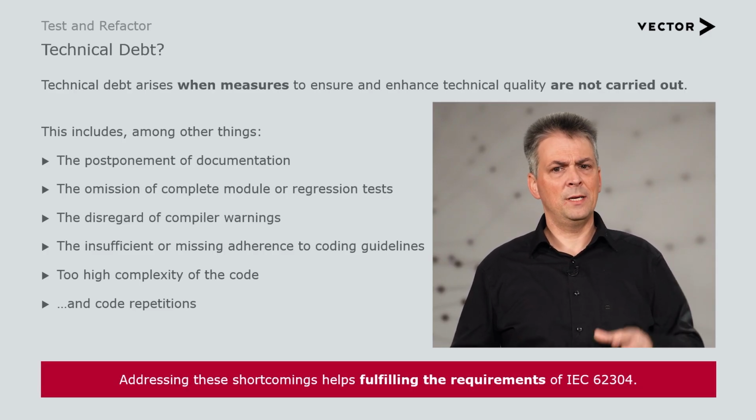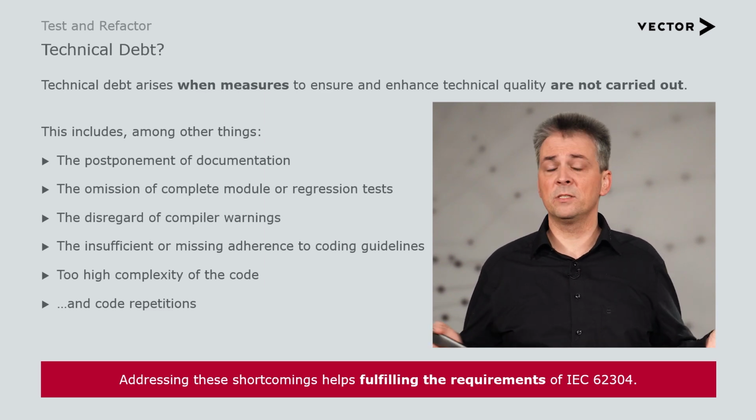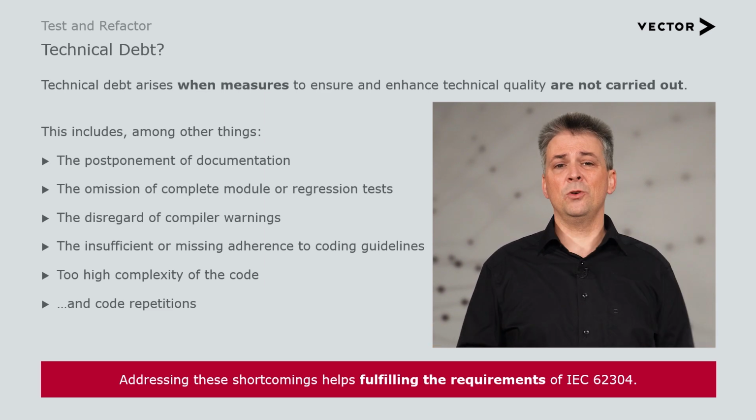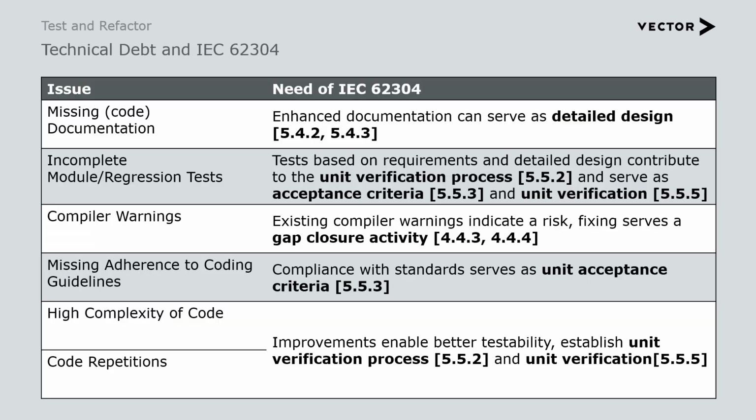But what has this to do with IEC 62304, medical device software? Addressing these shortcomings helps fulfilling these requirements. Let me explain. When we address missing code documentation, IEC 62304 is asking for detailed design, so for a clear documentation of your source code. So addressing this missing code documentation will help you addressing this need.